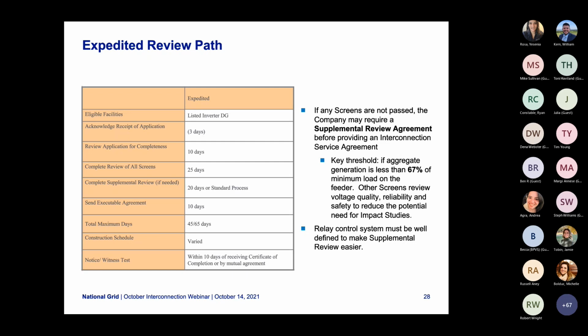It's a 25 business day turnaround for screens. If any screens are not passed, the company may require a supplemental review agreement before providing an interconnection service agreement. Key threshold is if the aggregate generation is less than 67% of the minimum load on the feeder. Other screens review voltage quality, reliability, and safety to reduce the potential need for impact studies. Relay control system must be well defined to make supplemental review easier.